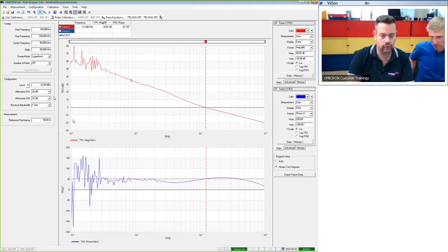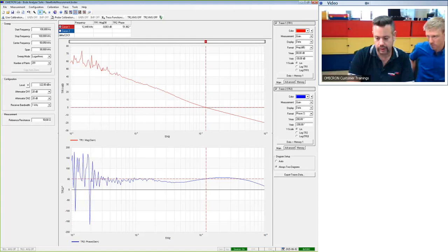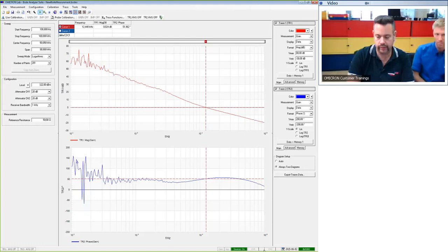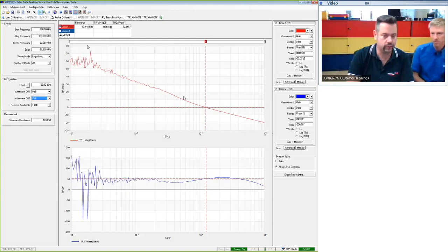First of all, we can look at the bars here at the right bottom corner of our screen, and here we see that there is not a lot of level at channel 1 and channel 2, so I can reduce the attenuators, and in fact, I can go even down to 0 dB. And as you can see, the curve is already getting smoother in some areas. But here in this area, we still have a lot of noise.